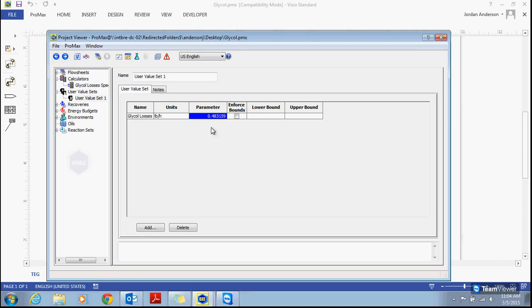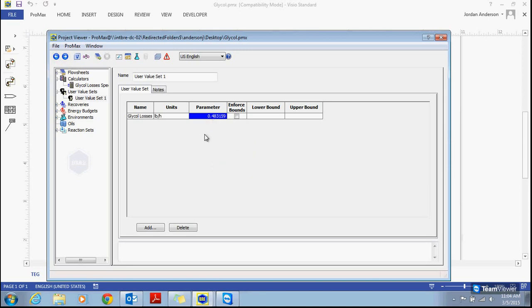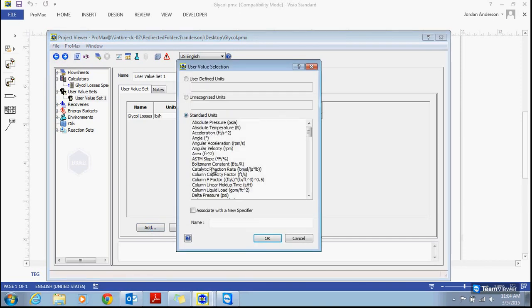The next variable we want to create is our glycol losses per million standard cubic feet of gas. We're going to take this variable that we've created and divide that by the amount of gas we're sending into our system. I'll choose add again. This time, instead of standard units, since we're using pounds per million standard cubic feet — units not in a standard configuration — I can come up here to user defined units and type in my units directly. This is going to be our glycol losses per million standard cubic feet of gas. That's the name of our variable and these are our units. I choose OK, then right-click to create a simple specifier. This specifier is going to equal my glycol losses over my gas flow.